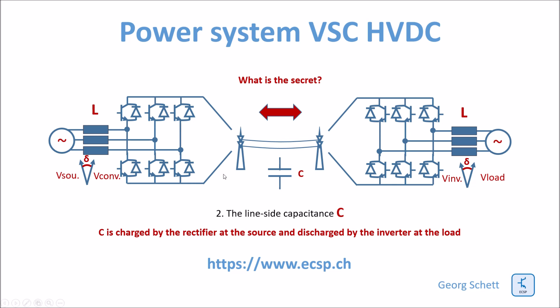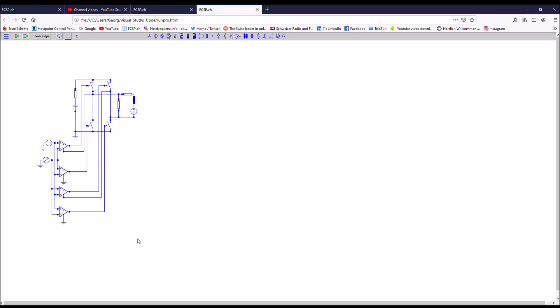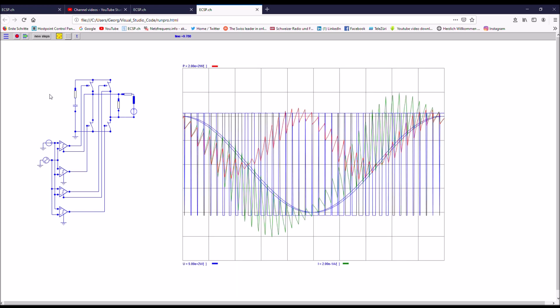The second part of the secret, typical for VSC technology, is that there is a large capacitor on the DC side of the converters — part of which is the line capacitance. These capacitors are charged or discharged by the converters on the load side and the source side. In the simulator model you can see the DC part of the converter, the line, and the additional smoothing capacitors. There is an active load which can feed power in both directions — back to the DC side or from the DC part into the system. The AC source represents the load side, along with the pulse width modulation controller.